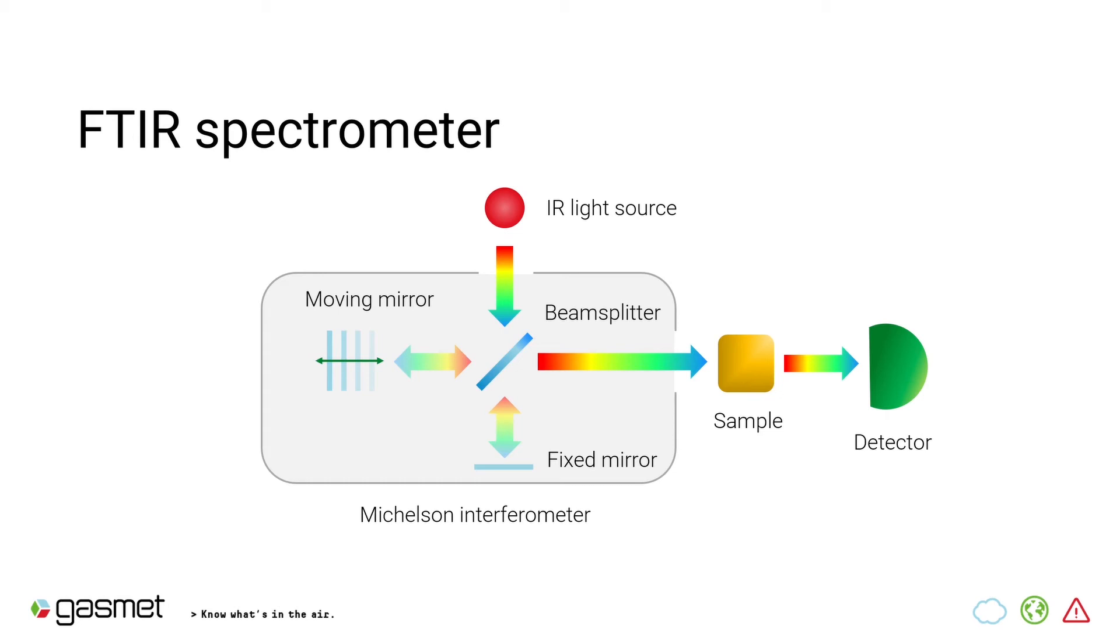Now, this is what we call a single beam operation. So, to get a reading of what happens to light without the sample, first we have to do a measurement without a sample. With our devices, this is normally done once a day. After this background measurement, we will compare all our other measurements to that background. So, what is accomplished by measuring everything at once?